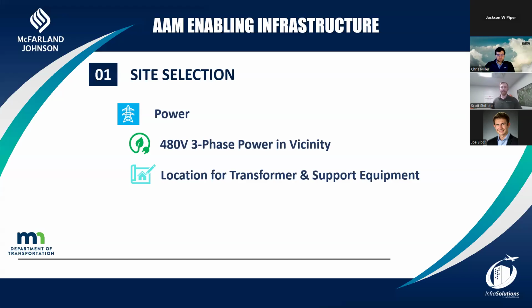The best way to look into that is to review as-builts. If you have overhead poles, is there three-phase on the wire? That won't guarantee it's 480 three-phase, but it's an indicator. Look at existing transformers within the vicinity - if you don't have record information, they'll have tags on them that say 480 volt three-phase. Those are just a couple of indicators you can look at. Also consider where you're going to put the transformer and support pads - it's not just a charger, there are pieces of support equipment that go along with it.